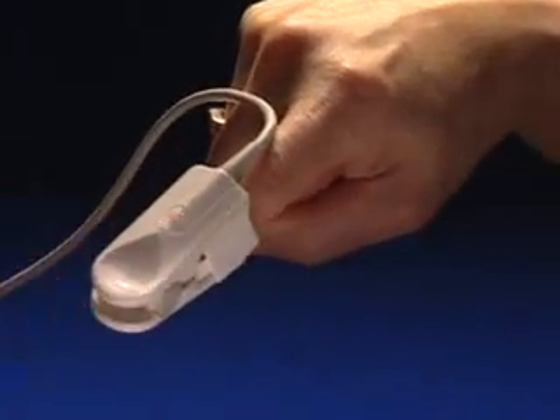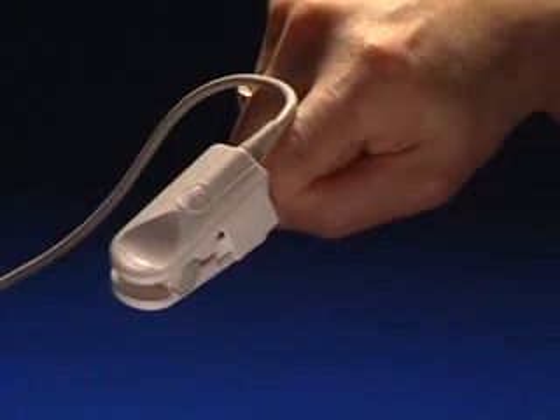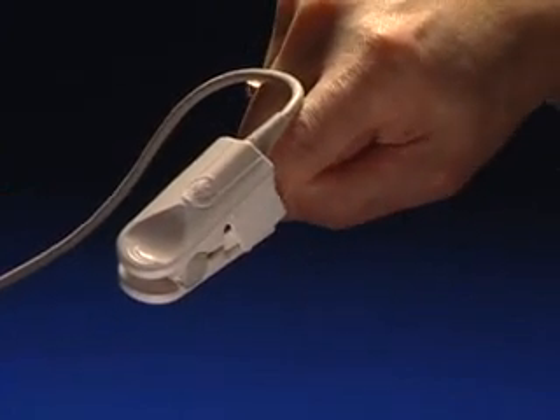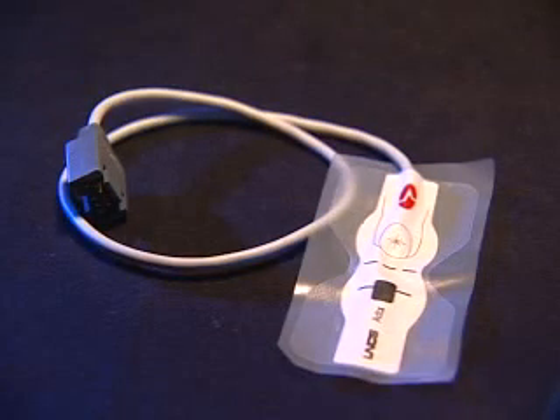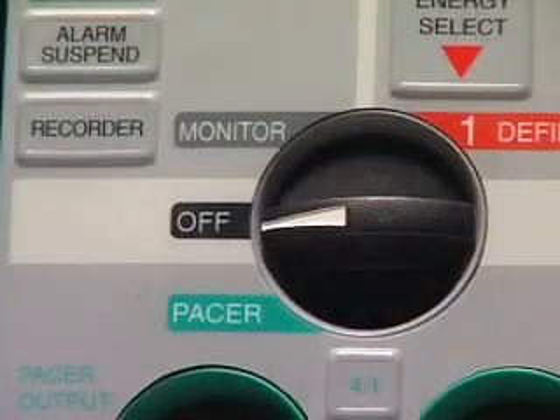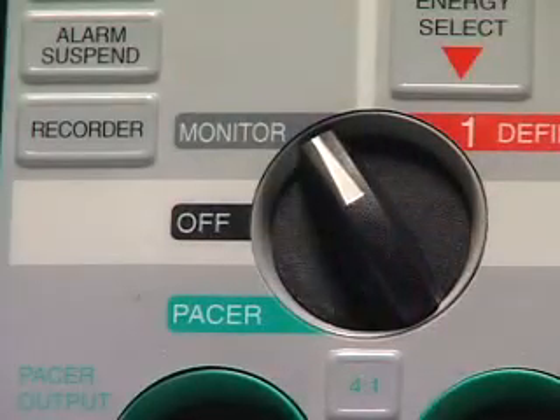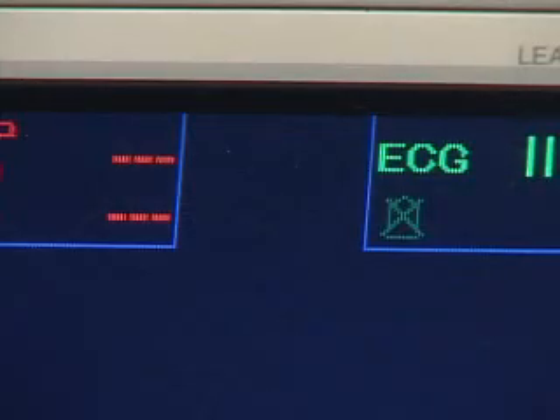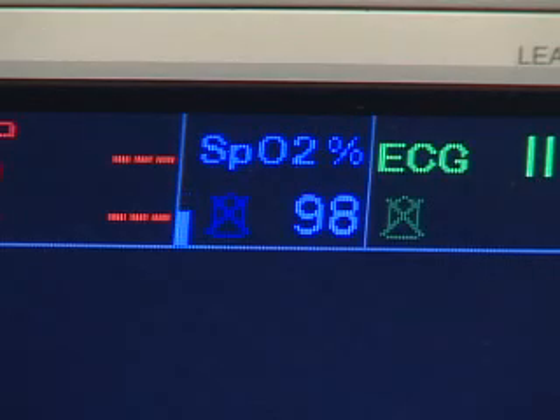Choose a patient site that is well perfused and restricts a conscious patient's movements the least. When using a disposable sensor, it should be placed according to the instructions on the package. Turn the E-Series selector switch to Monitor for advisory and manual devices. A dashed line will be displayed in the SpO2 field until the patient pulse is detected. Once the measurement has been established, the saturation values will be displayed in the numeric field box.